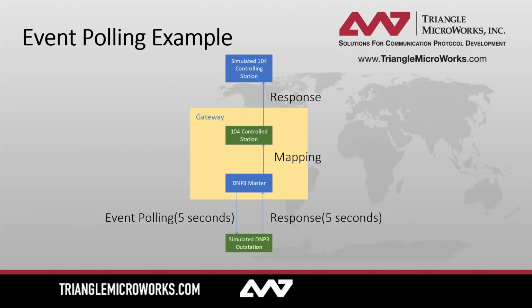So this is the next system we're going to take a look at. We have our controlling station as a 104 device, and our simulated DNP3 outstation, again in DTM, as our IEDs in the network. This time we're going to be using event polling, so I can show you how to configure that. Because event polling has much less data, we can decrease the polling period to every 5 seconds rather than the 15 seconds we looked at before. Then you'll get responses as the events change, as data is changing. That mapping will move over, and we'll have responses up to our control station.